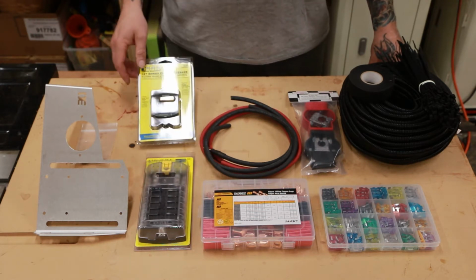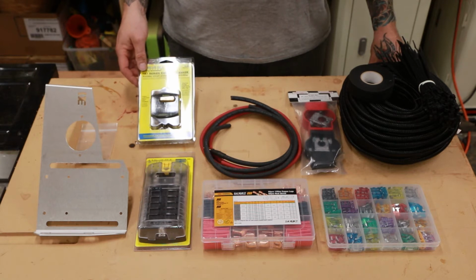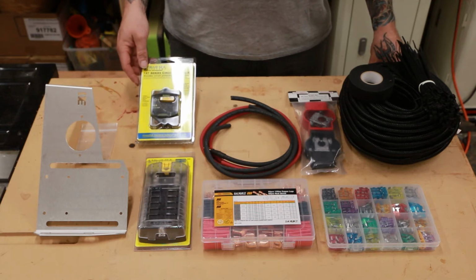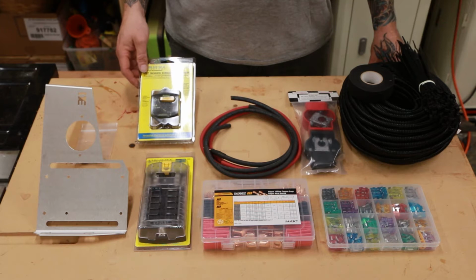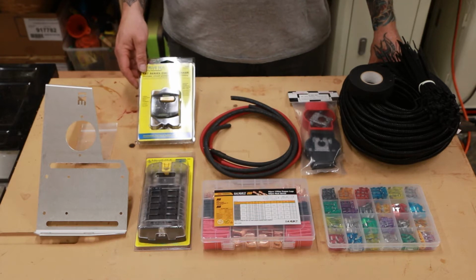We'll also need a circuit breaker to protect our new fuse block and the accessories that will be plugging into the auxiliary panel. When selecting your circuit breaker, add up your proposed amperage of all your accessories to come up with the desired amperage you want for your breaker. I went with a 90 amp breaker, as I'll be using this panel primarily for lighting and switch relays.